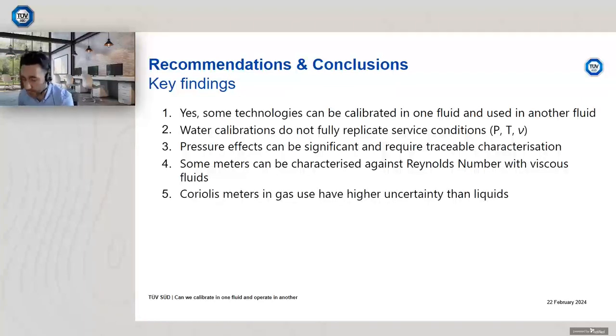But be mindful, you want to obviously be at a reasonable velocity. And for differential pressure meters, you obviously want to achieve a reasonable differential pressure. You can't simply operate at very low Reynolds numbers, but only be measuring, say, 5 or 10 millibar. That doesn't make sense. You're going to have a very large uncertainty. You would still need to be using, let's say, a medium viscosity fluid that gets you a reasonable differential pressure so that you're operating with a reasonable uncertainty.